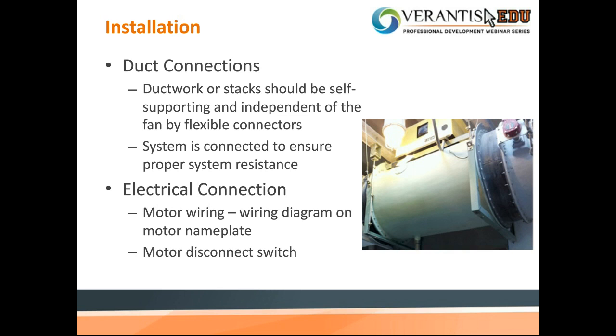Electrical connections, motor wiring. Follow the motor wiring on the nameplate. We have seen an occurrence where we have a backward inclined fan that the motor was reversed in its wiring and turned into a forward inclined fan. Yes, it's still going to move air, but it will not move what is required of the system. So make sure your wiring is proper, as well as the motor disconnect switch. What good is a motor disconnect switch if it's not wired properly? So definitely items that you want to make sure are done properly.